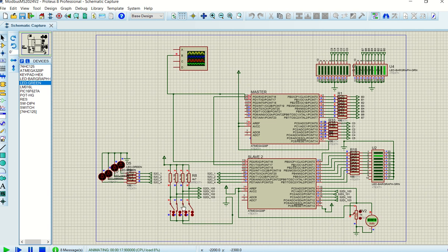If I make this bit high by opening the switch again, it's going to be 1101, and there you go. So first of all, the master is continuously asking, and the slave is continuously responding. But as you can see, 1011, and it reflects here 1011. So the master knows exactly what's happening with the discrete inputs on the slave 2 that we have here. And this is the functioning of Modbus function number 2, where we can also read discrete input values.